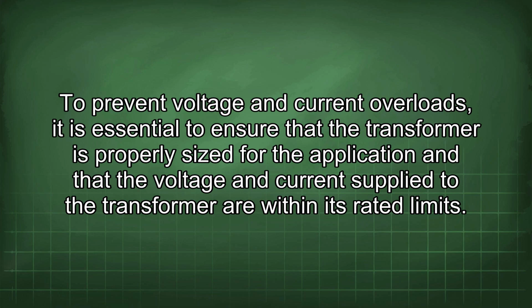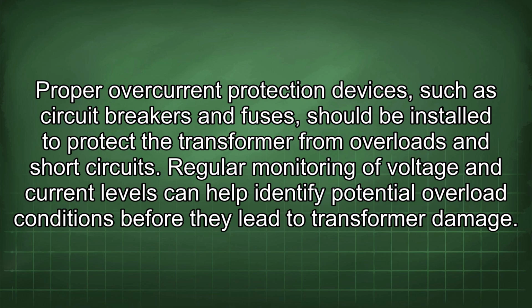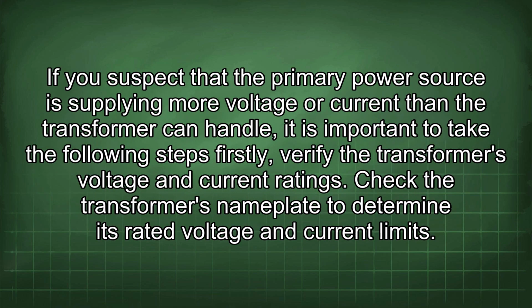To prevent voltage and current overloads, it is essential to ensure that the transformer is properly sized for the application and that the voltage and current supplied to the transformer are within its rated limits. Proper overcurrent protection devices, such as circuit breakers and fuses, should be installed to protect the transformer from overloads and short circuits. Regular monitoring of voltage and current levels can help identify potential overload conditions before they lead to transformer damage. If you suspect that the primary power source is supplying more voltage or current than the transformer can handle, it is important to take the following steps.